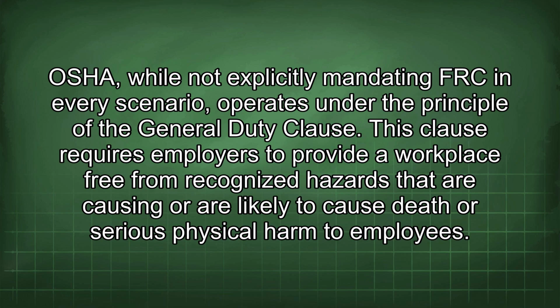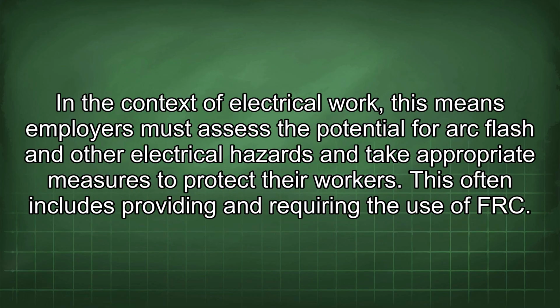OSHA, while not explicitly mandating FRC in every scenario, operates under the principle of the General Duty Clause. This clause requires employers to provide a workplace free from recognized hazards that are causing or are likely to cause death or serious physical harm to employees. In the context of electrical work, this means employers must assess the potential for arc flash and other electrical hazards and take appropriate measures to protect their workers. This often includes providing and requiring the use of FRC.